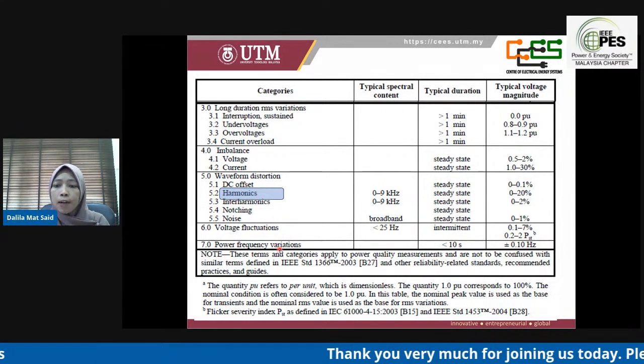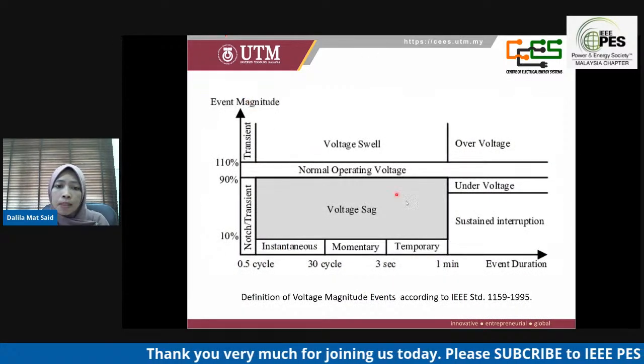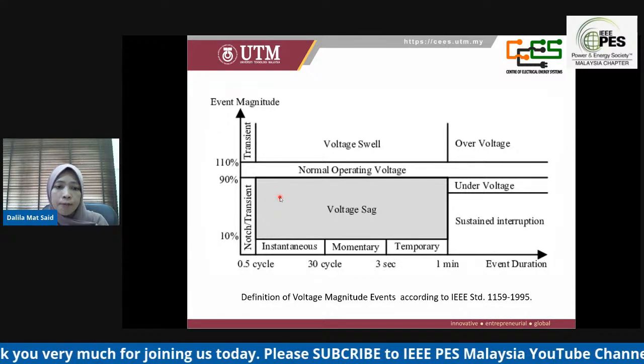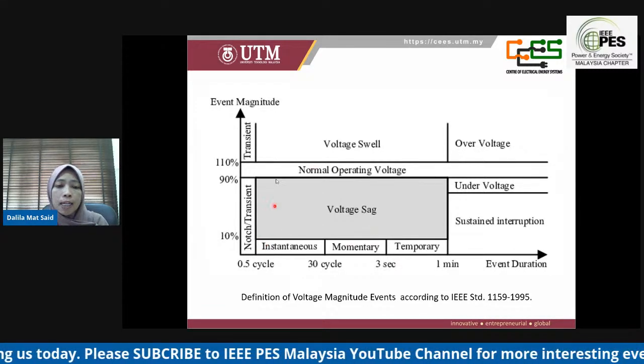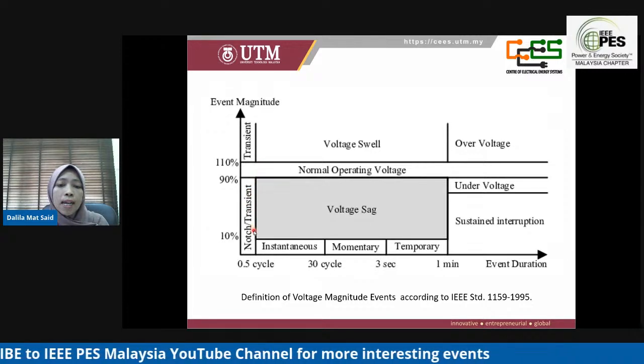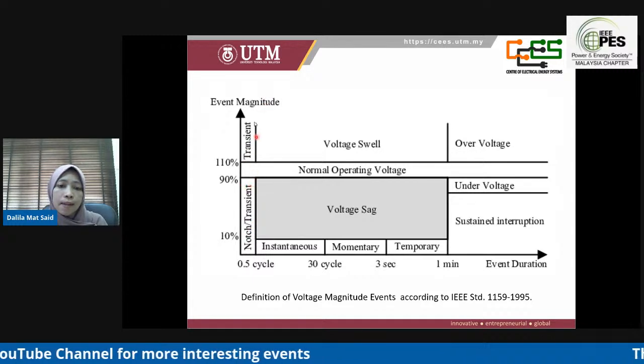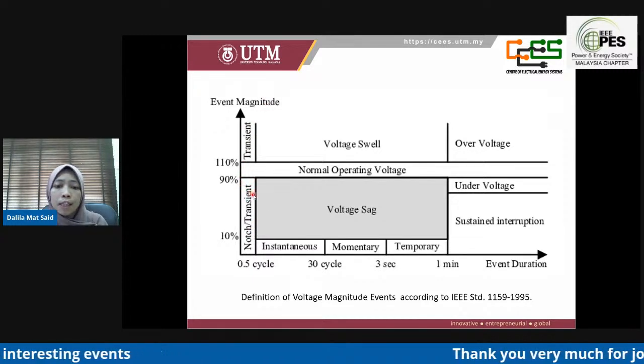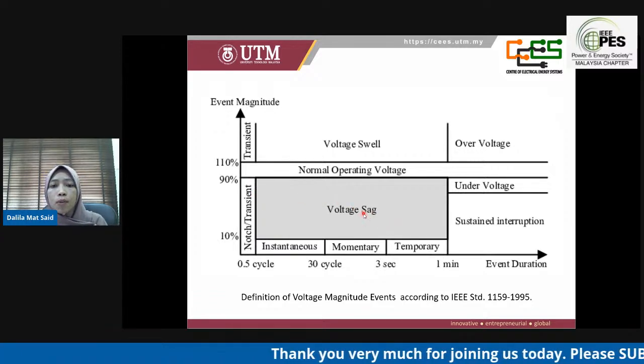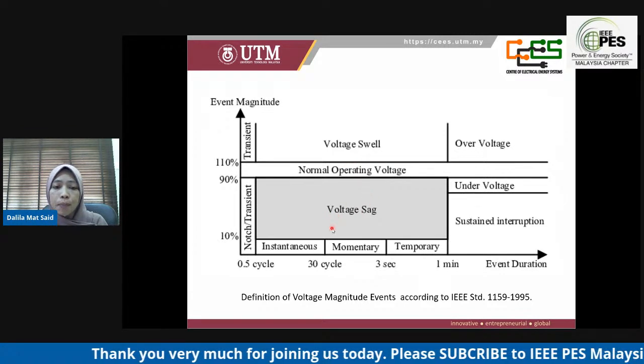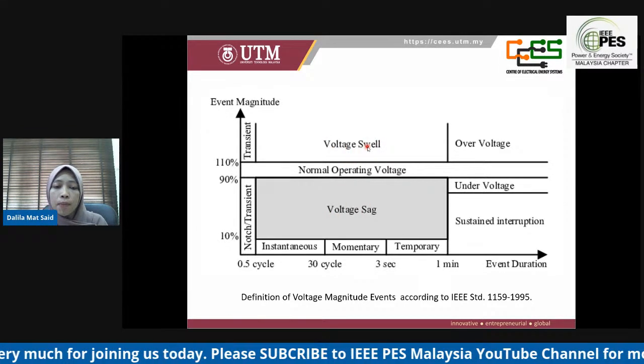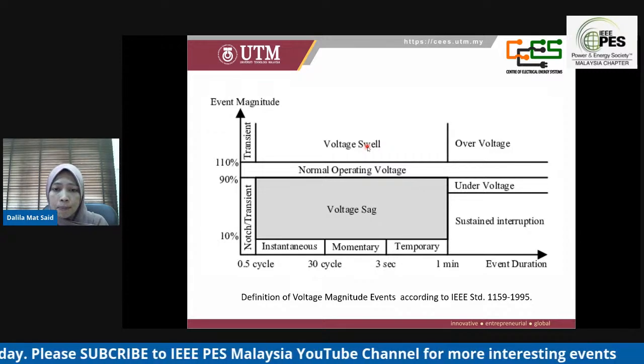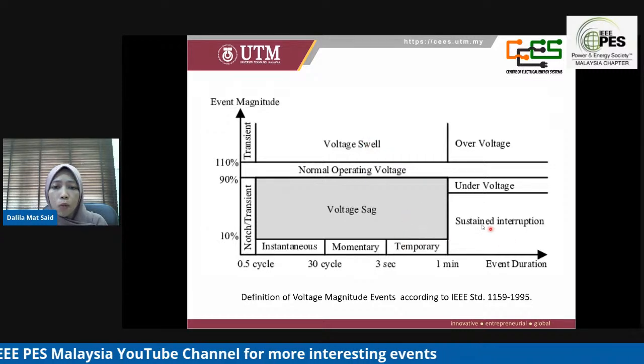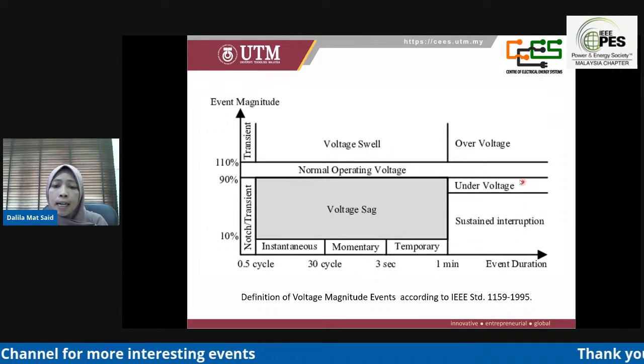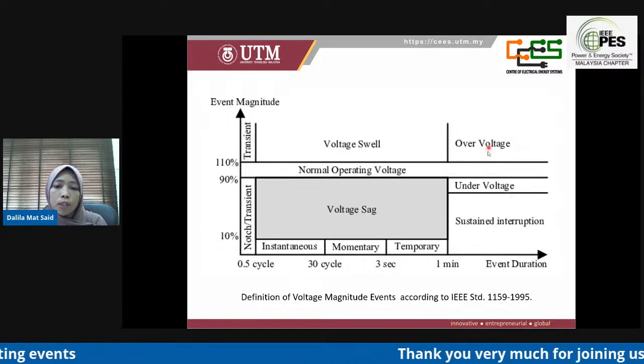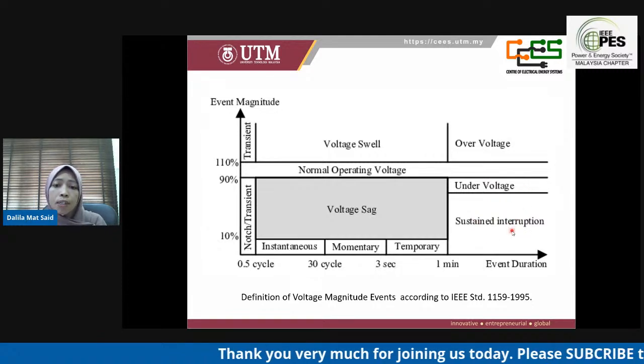And from this graph, we can see the classification of the instantaneous part, where the event that occurs for less than half a cycle we consider as a transient. So for the event starting from half cycle to 1 minute, we can consider it a voltage sag if the magnitude is between 10 to 90%, and a voltage swell if the magnitude is above 110%. And for the event that occurs more than 1 minute, we can consider it a sustained interruption, under voltage or over voltage, that has been classified under long duration variation.